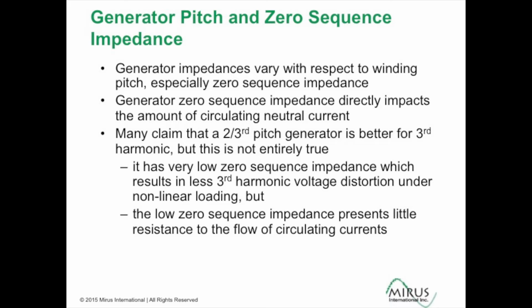So although it doesn't produce much third harmonic voltage, when there is third harmonic voltage in the system, or if there are voltage waveforms being paralleled that are not in the same wave shape, then the 2/3 pitch generator provides little impedance to the flow of the circulating current, so more circulating current will flow in that application. Most generator manufacturers today sell primarily 2/3 pitch winding configurations. So when paralleling with generators of other pitch factors or a utility transformer, the low zero sequence impedance will actually allow more neutral circulating current to flow.